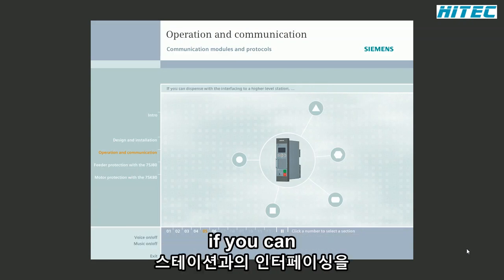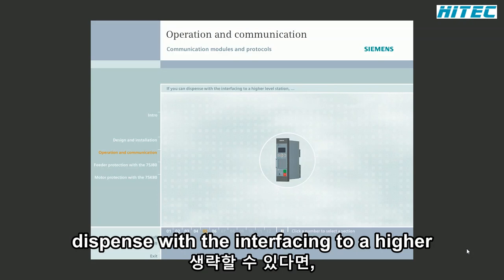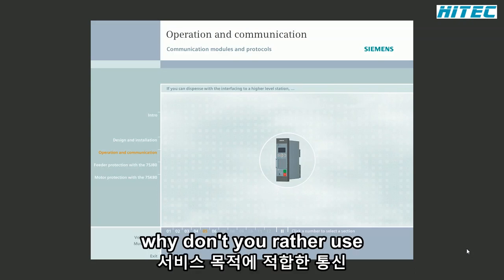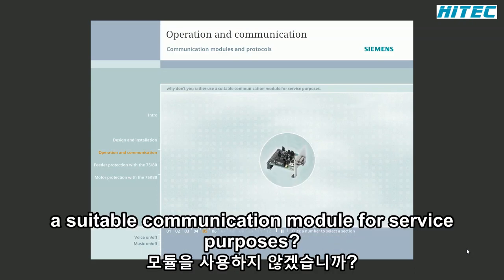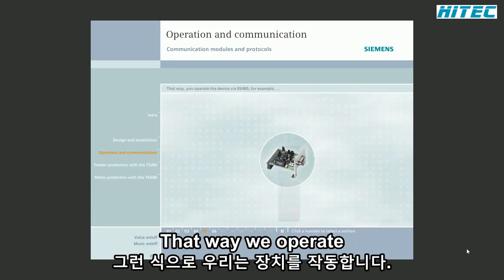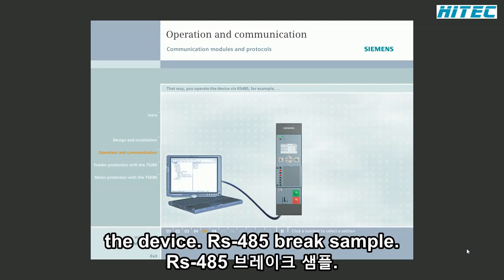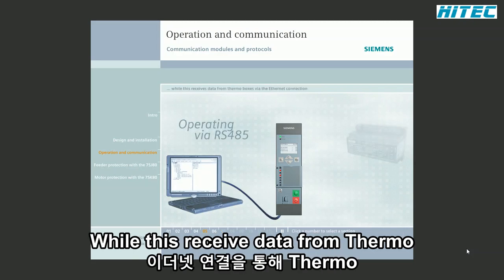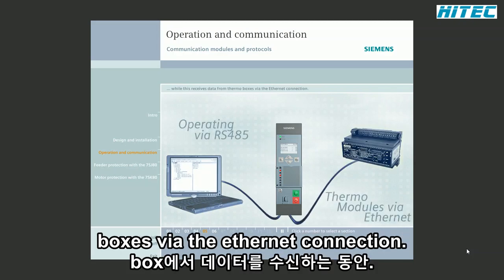Oh, and by the way, if you can dispense with the interfacing to a higher level station, why don't you rather use a suitable communication module for service purposes? That way, you operate the device via RS-485, for example, while this receives data from thermal boxes via the Ethernet connection.